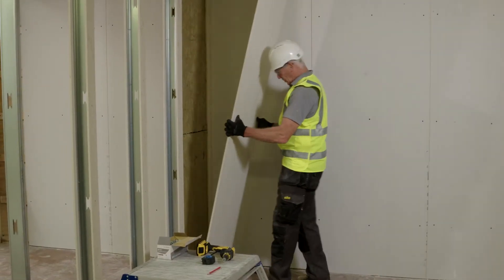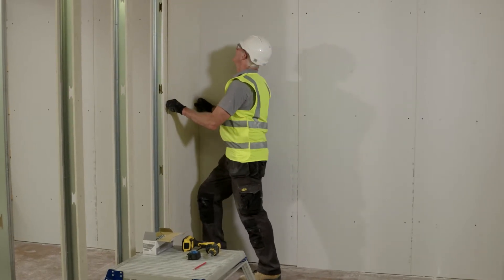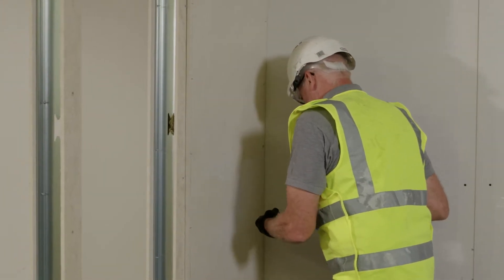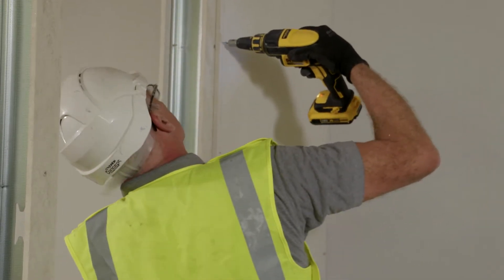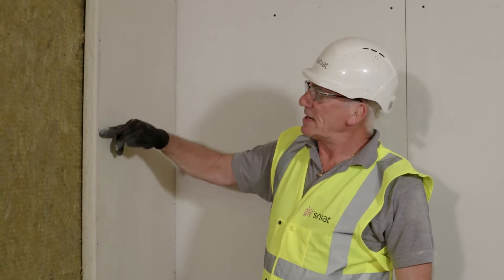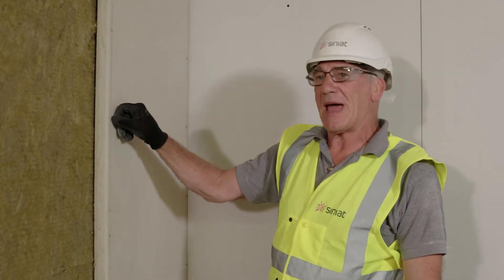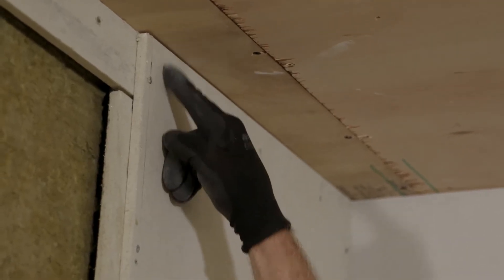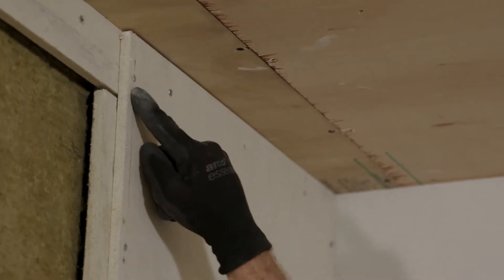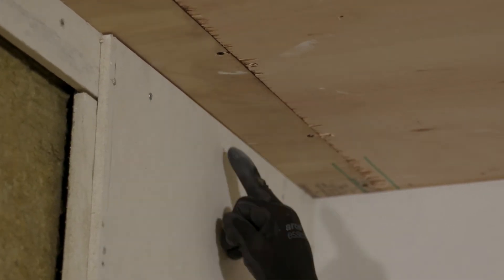I'm now ready to install my Supalux boards. The distance between fixings is 250 millimeters, and fixings also need to be 12 millimeters in from the edge of the board. Corners are important — the fixing needs to be 50 millimeters down from the ceiling height and 100 millimeters in from the edge, with fixings still 250 millimeters apart into the head track and the base track.